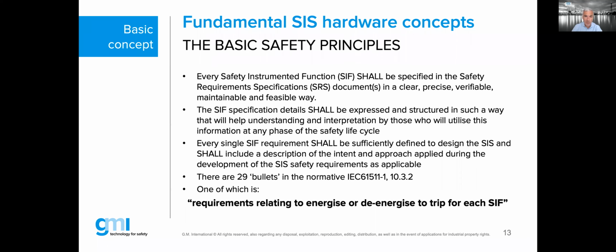As a majority of you probably will know, for every safety instrumented function, which is called a SIF, you shall specify very specifically, in a document called the Safety Requirement Specification, exactly what this safety function has to do. One of the items is the requirement relating to whether you energize your output to activate the safety function, which is very rare to see, or de-energize the output of your system, to take the energy away, to enable it to go to a safe position of your safety function.